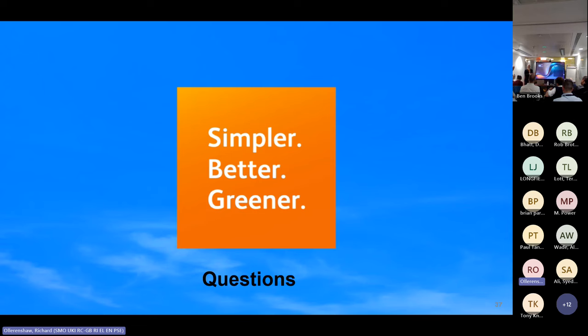So some neutrals are in places where they're not really needed. They're just there because of phase separation, and you can take those away fairly easily. But for example, the ones at the west end of Leeds Station, you'd probably want to keep those to segregate an incident on the Transpennine route from an incident on the main Leeds to London main line. It can be done with switches, but it's not an easy answer, if that makes sense. So you can parallel up without getting rid of every neutral section. Thanks.